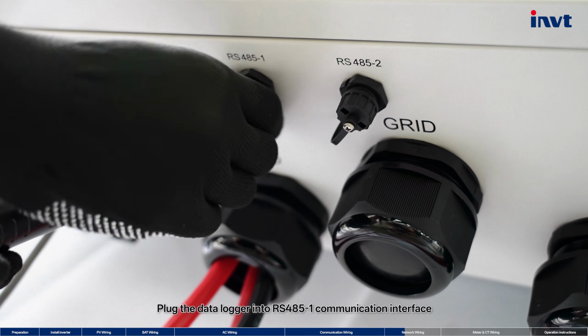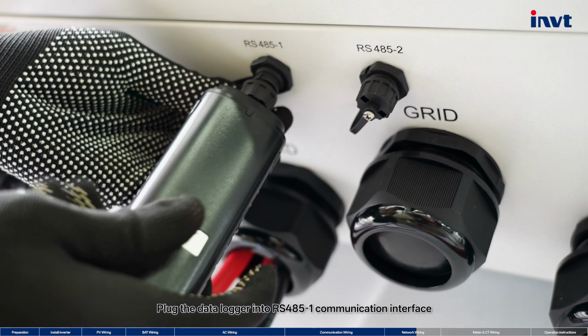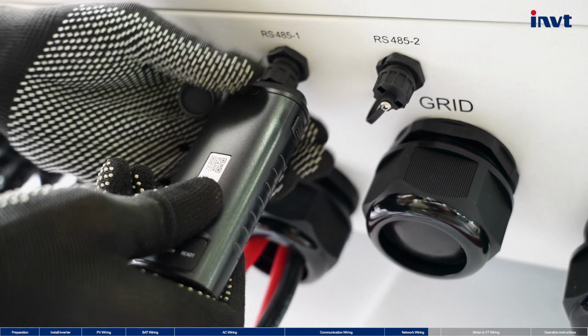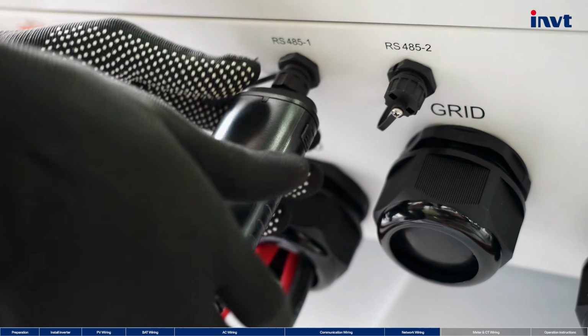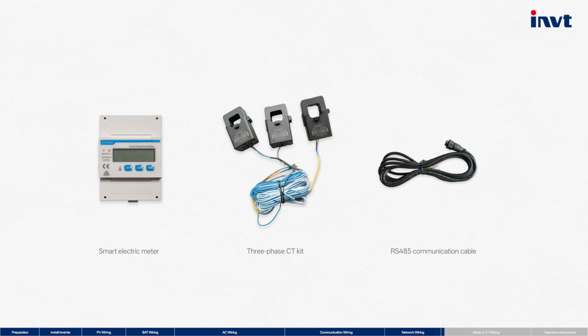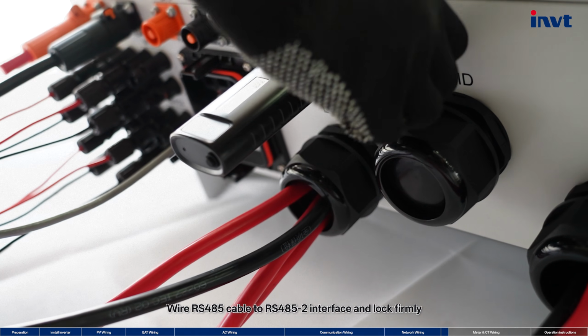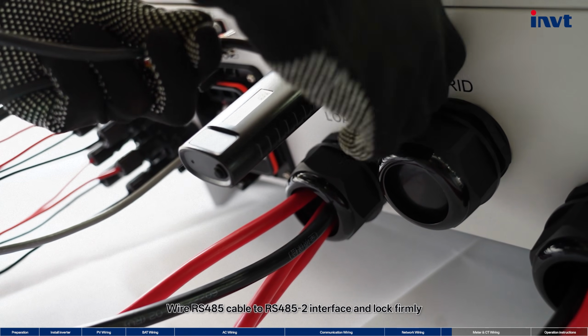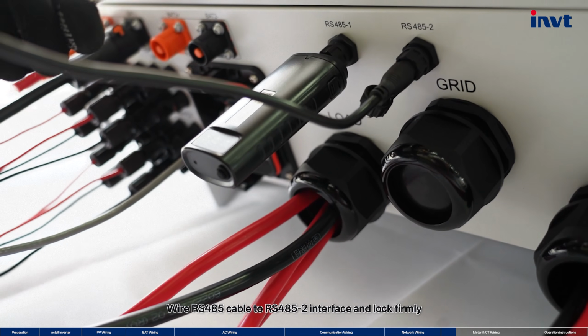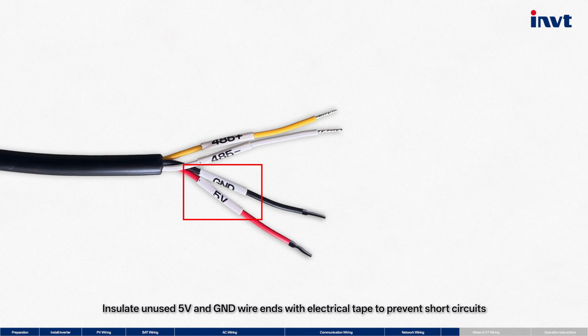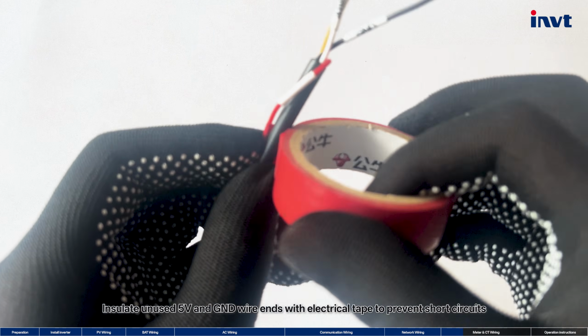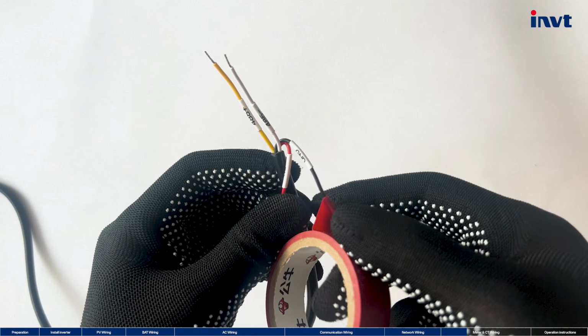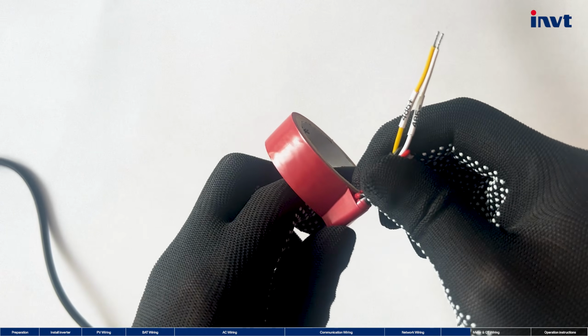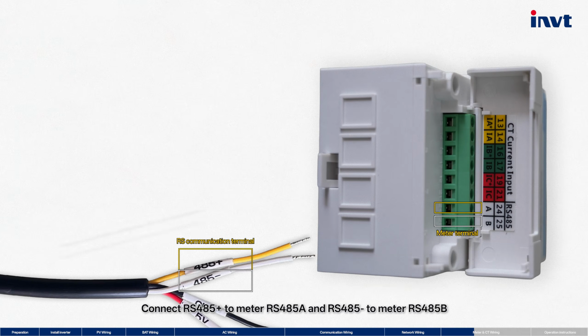Plug the data logger into RS485-1 communication interface. Fasten tightly. Wire RS485 cable to RS485-2 interface and lock firmly. Insulate unused 5V and GND wire ends with electrical tape to prevent short circuits. Connect RS485 positive to meter RS485A and RS485 negative to meter RS485B.